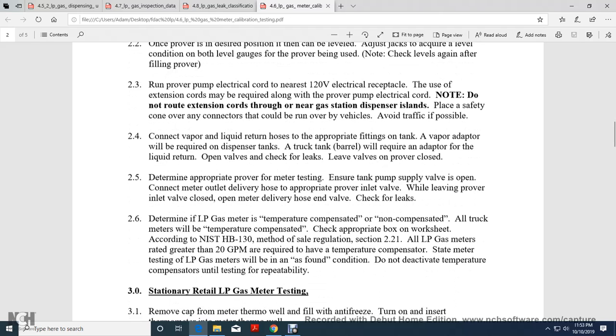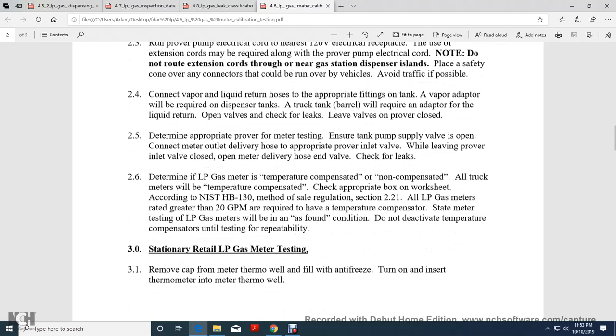Connect the vapor and liquid return hose with the appropriate fitting on the tank, and the vapor adapter as required with the dispenser. Trucks will require an adapter for the liquid return. Open the vapor valve and check valve, with the prover liquid valve closed. Determine the appropriate prover for meter testing. Ensure the tank pump supply valve is open. Connect the meter outlet delivery hose to the appropriate prover inlet valve, leaving the prover inlet valve closed.